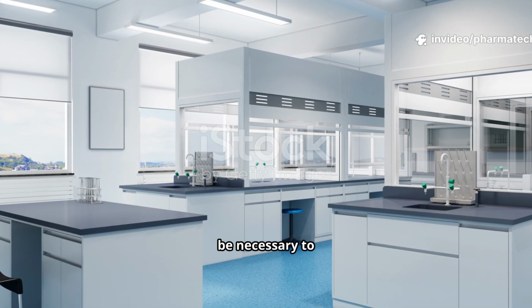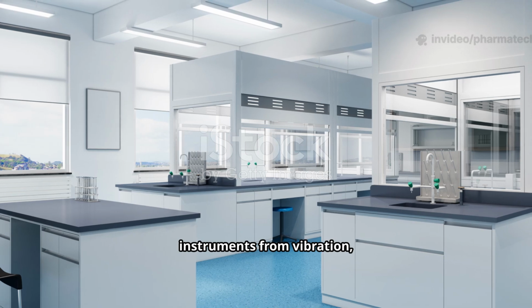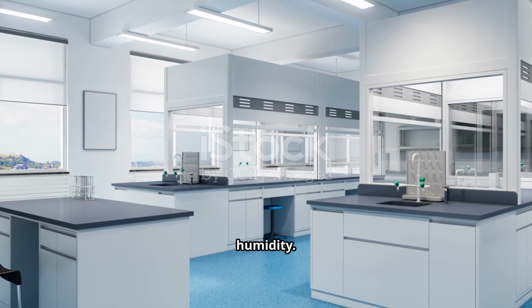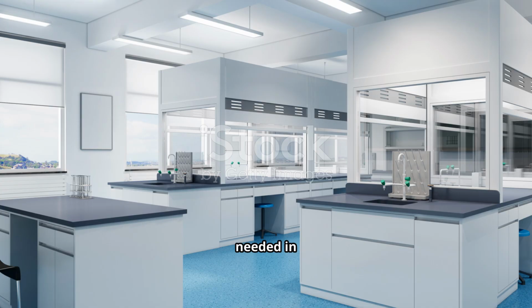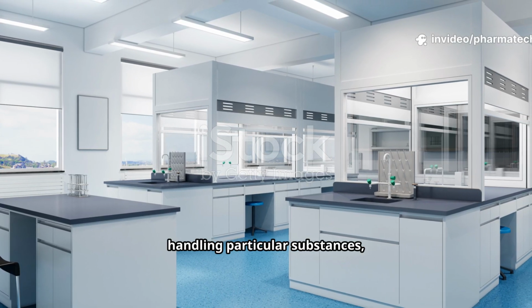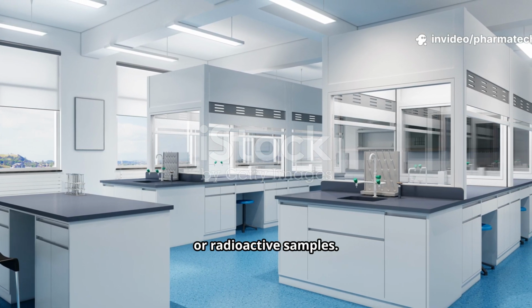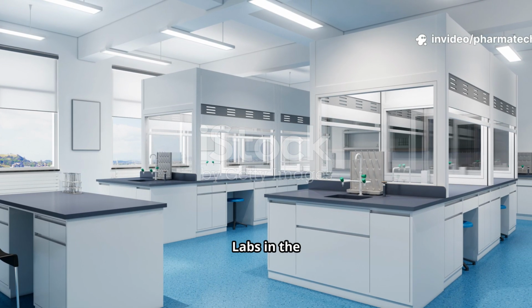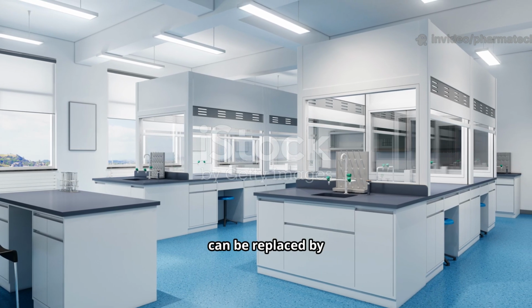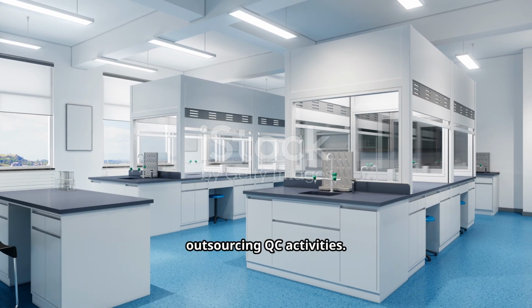Separate rooms may be necessary to protect sensitive instruments from vibration, electrical interference, humidity. Special requirements are needed in laboratories handling particular substances, such as biological or radioactive samples. Quality control labs in the manufacturing site can be replaced by outsourcing QC activities.